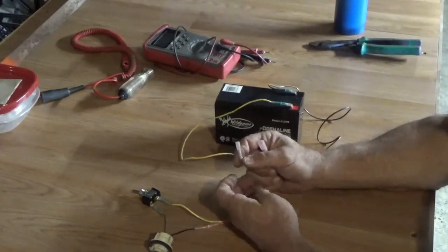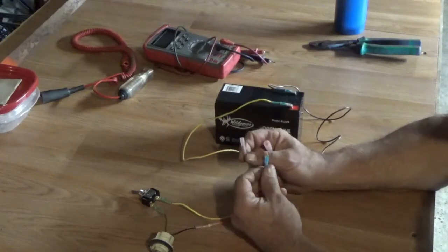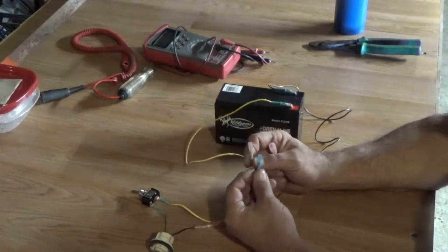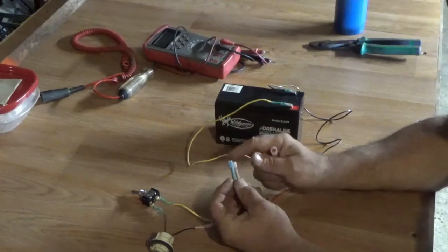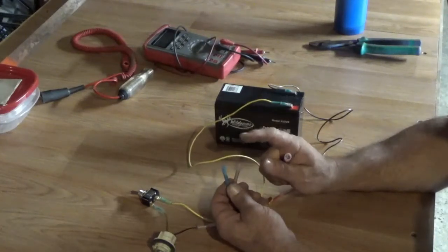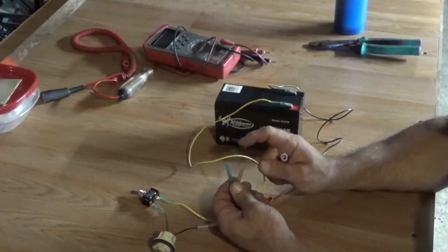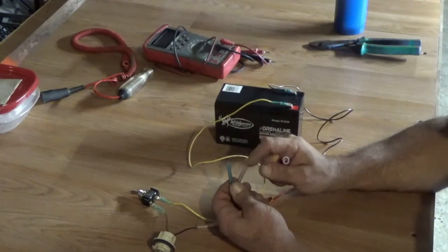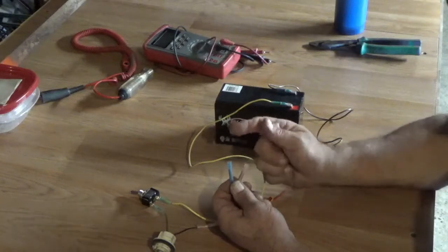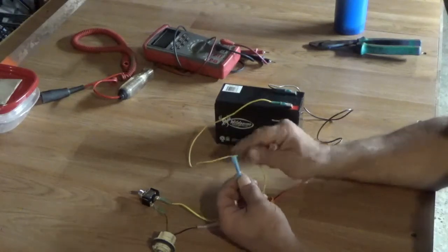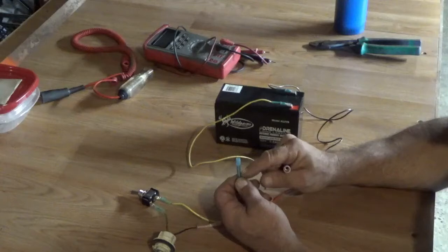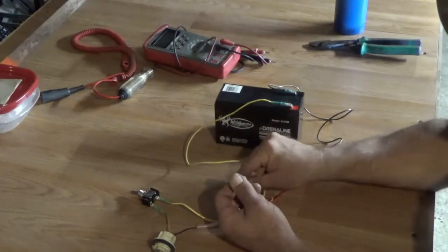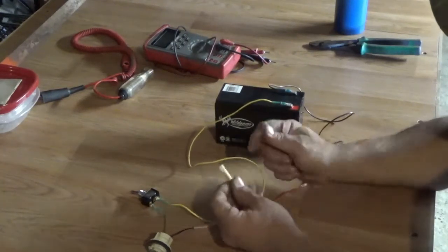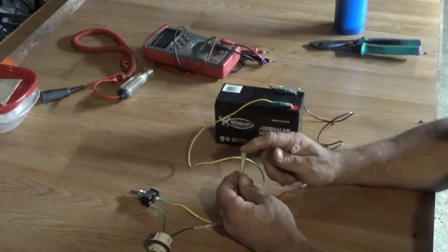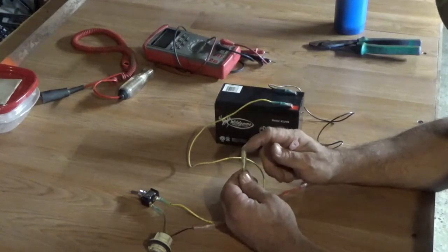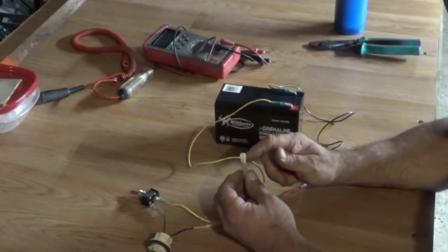These are heat shrink connectors. These should be used anytime your system may encounter a wet environment. And the colors are the ones that I buy anyway. These pink ones are for smaller gauge wires, 18 gauge. The blue ones are for a little bit heavier wires, like 14 gauge. The yellow ones are for like a 12 gauge. If you're real careful and patient, you can get a 10 gauge in here, but it's tight.